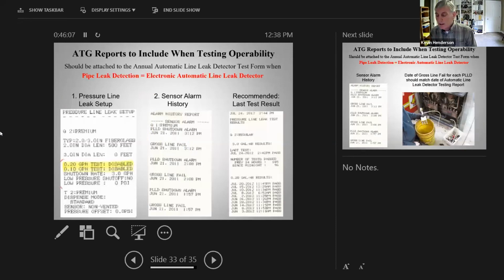So again, with electronic leak detectors, you need to be able to show that you did in fact cause that electronic leak detector to go into alarm, that you did verify that it is capable of seeing a 3 gallon per hour leak. And so the way that you do that again, you need to be able to show tank gauging reports. And here's some examples again from Veeder. You look at the setup report for the PLLD, and you'll see that this one actually has 500 feet of fiberglass pipe, which is kind of unusual.